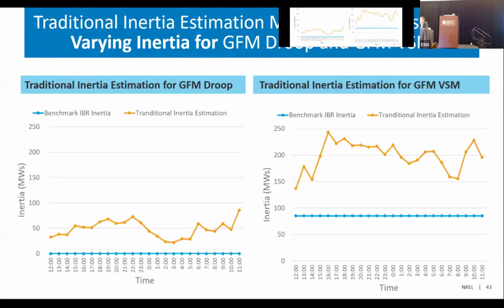Here you go. So the left figure is the grid forming droop. The right is the grid forming VSM. The orange line is the traditional inertia estimation result, and the blue line is what we call the benchmark of the IBR inertia. For the grid forming droop, you can see there is no inertia control block built in, but it still provides very good inertia contribution, I should say, in this context. This is only a 30 megawatt grid forming unit, but it can provide 30 to 70 megawatt seconds of inertia to the grid. And when we move to the right, it's the grid forming VSM.